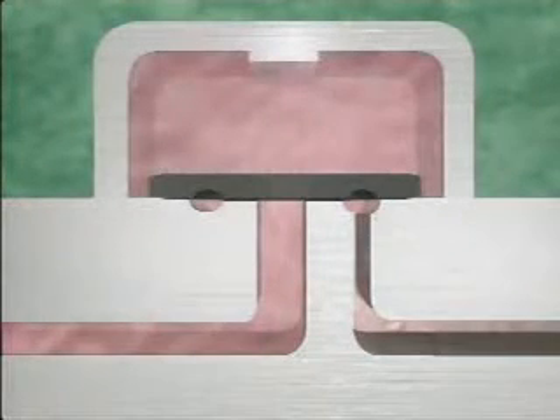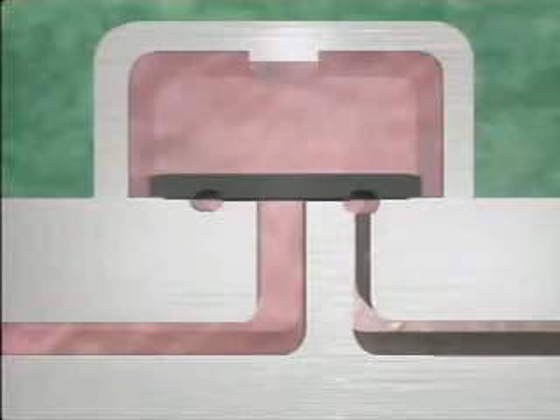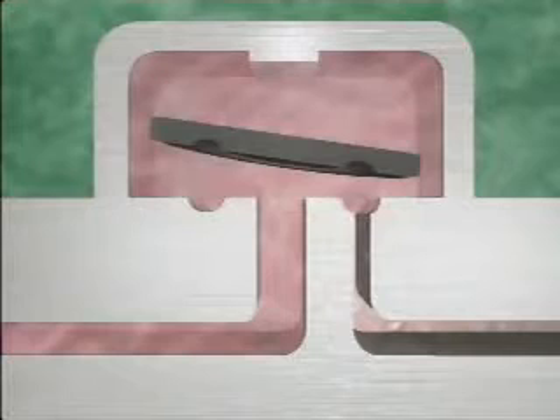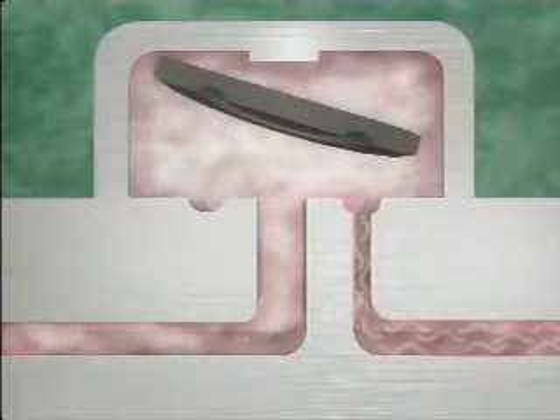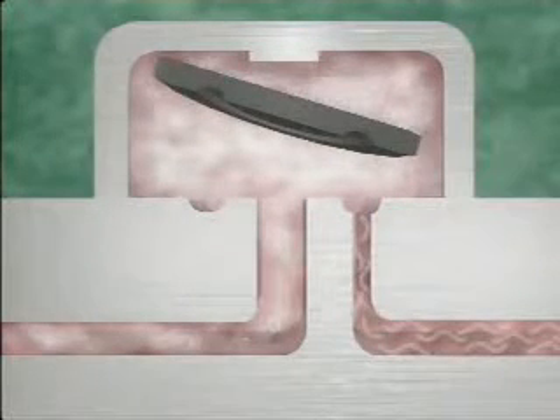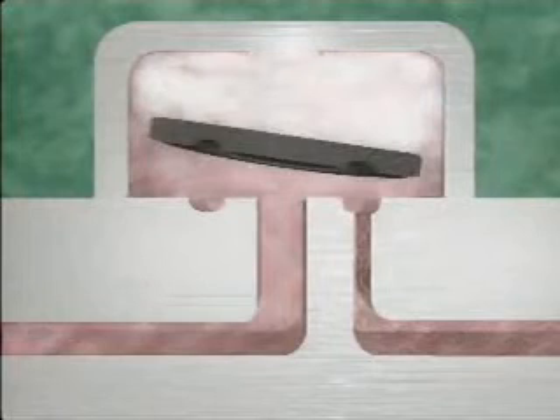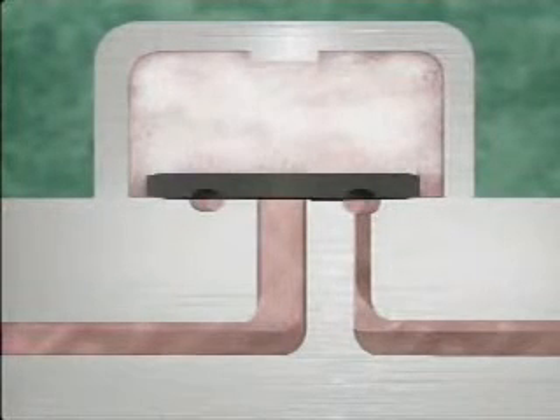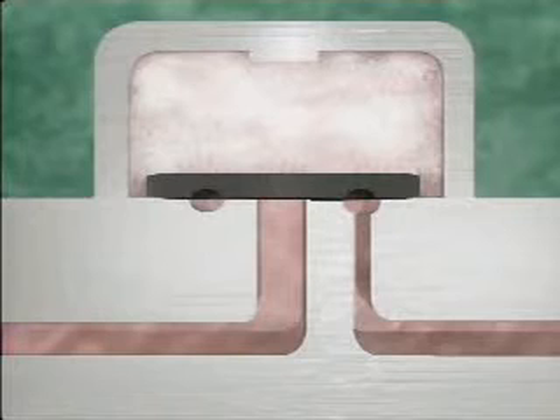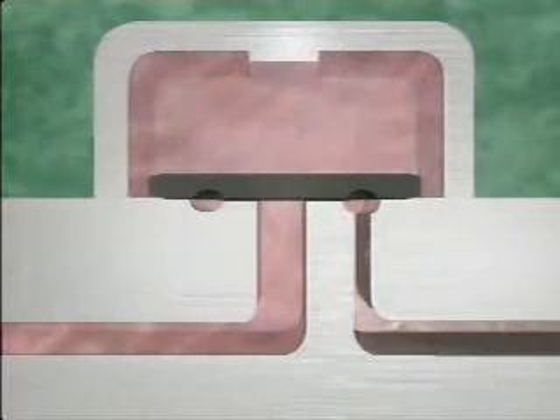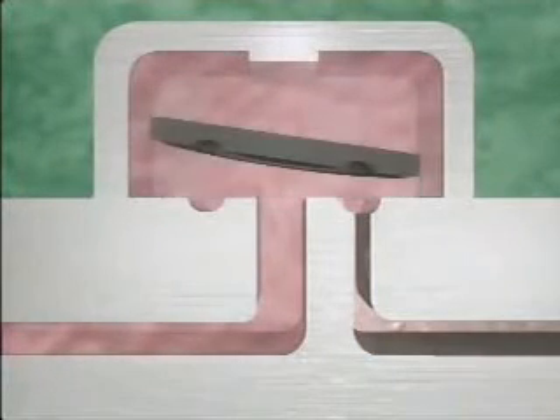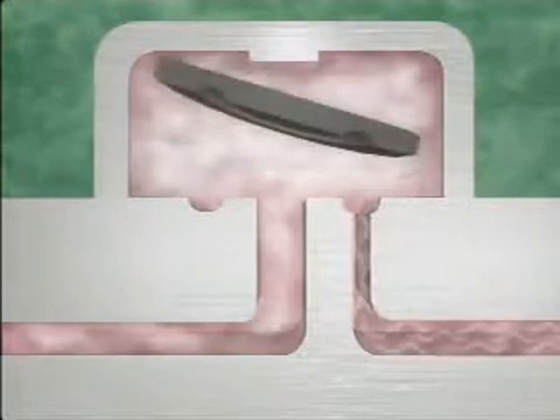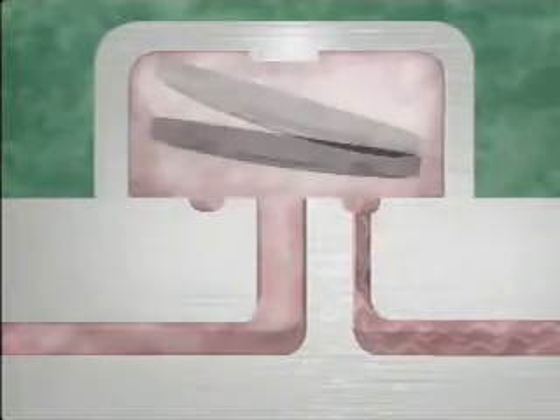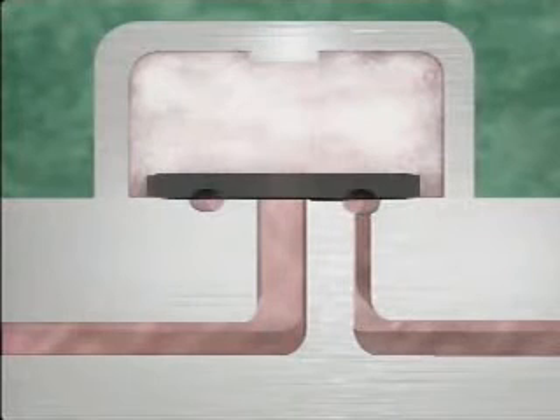When this steam condenses, changing to a liquid state, and the pressure above the disc becomes low enough, the disc rises and condensate flows out, until velocity and pressure conditions within the trap again cause the disc to snap down on the seating surfaces, closing the trap. If the temperature and pressure at the trap inlet remain constant, a disc trap opens and closes at regular intervals. That is, the trap operates on a time cycle.